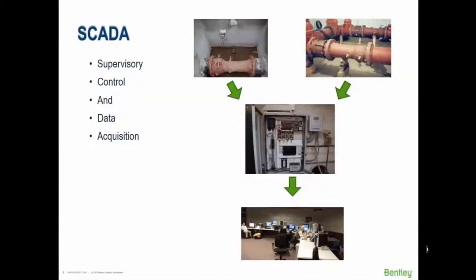The basic tool of operators in terms of hydraulics in the control room is integrating with the SCADA system. SCADA stands for Supervisory Control and Data Acquisition. It's the process of getting data — in this case from Venturi meters — taking that data, which is usually some type of analog differential pressure, converting it to a digital signal at an RTU, and sending that back to the control room for display. That's part of what the SCADA system does, but it does a lot more than that.